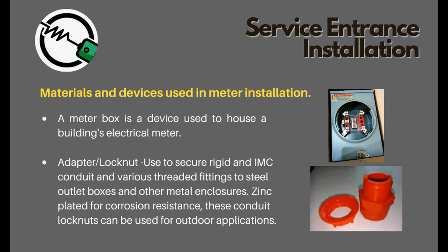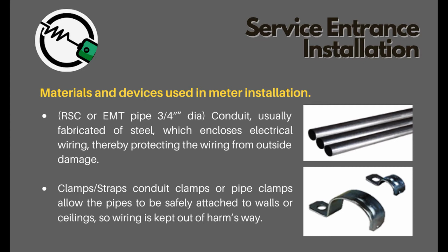Materials and devices used in meter installation. A meter box is a device used to house a building's electrical meter. Adapter, lock nut: used to secure rigid and IMC conduit and various threaded fittings to steel outlet boxes and other metal enclosures. Zinc plated for corrosion resistance, these conduit lock nuts can be used for outdoor applications. RSC or EMT pipe, 3/4 steel conduit, usually fabricated of steel, which encloses electrical wiring, thereby protecting the wiring from outside damage. Clamps, straps. Conduit clamps or pipe clamps allow the pipes to be safely attached to walls or ceilings, so wiring is kept out of harm's way.